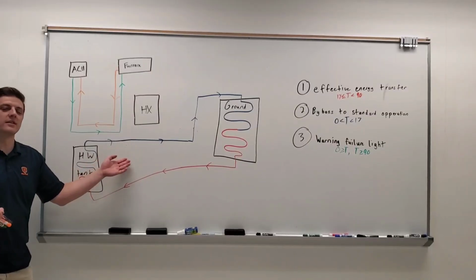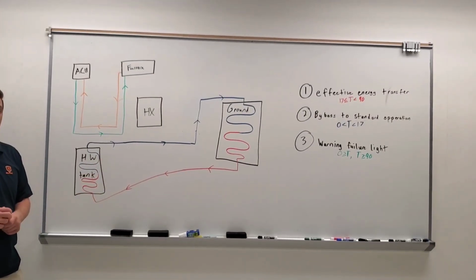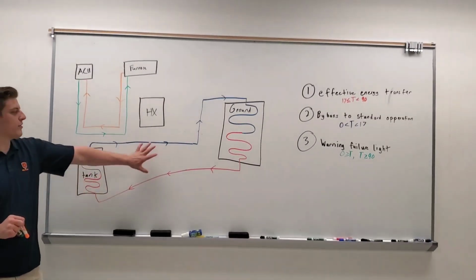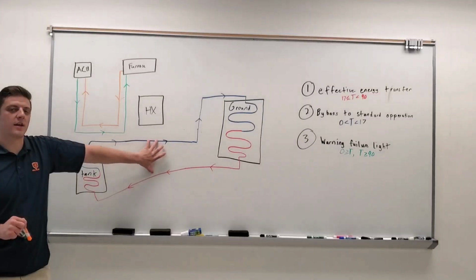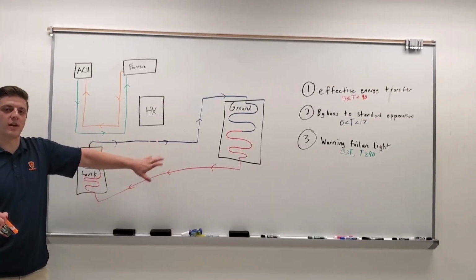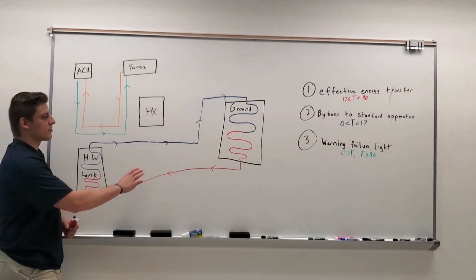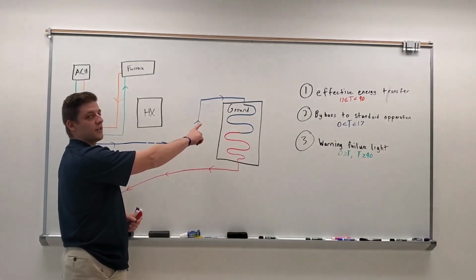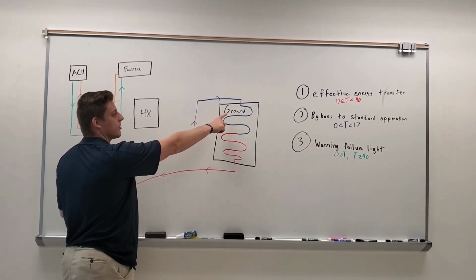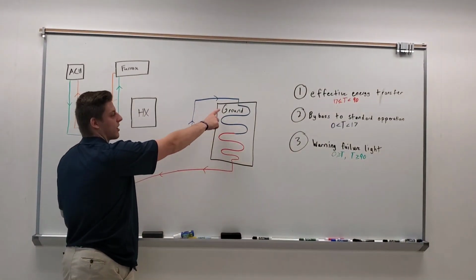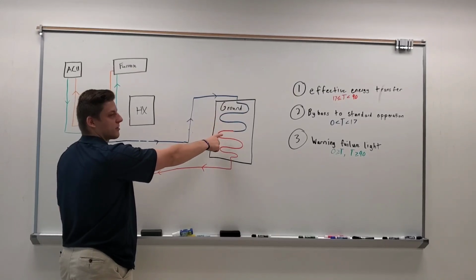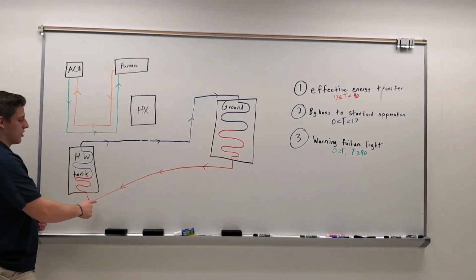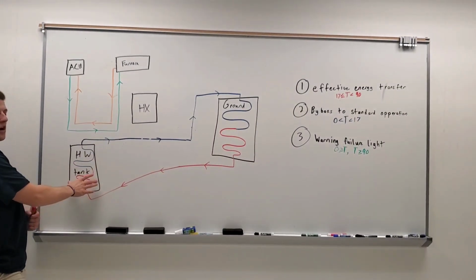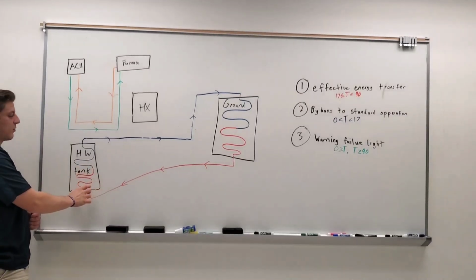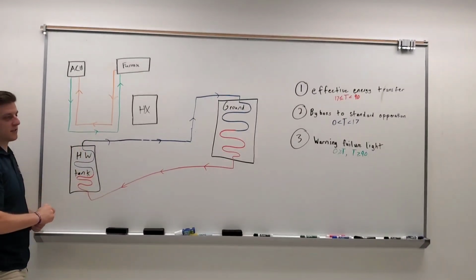This is what the system in residential homes currently looks like with a ground source heat pump. We removed the ground source heat pump, that would roughly be right here, to show a simplified loop to explain our concept. Basically, the ground source heat pump pumps the water through the ground as cold water, which the ground heats up and preheats, and then it comes through the ground source heat pump into our hot water storage tank.